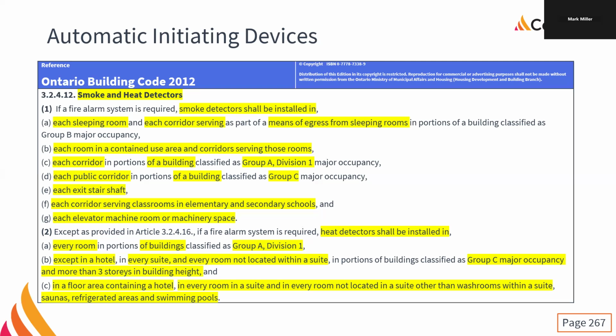Then we also need to put smoke detectors in each room in a contained use area and corridors serving those rooms. So if we have a ward that is locked down for mental health or acquired brain injury, Alzheimer's, dementia, anything like that, right? Oh no, sorry, that's impeded egress zones. Contained use areas, that's our jail cells, right? We have to put a smoke in there. And then all the corridors.